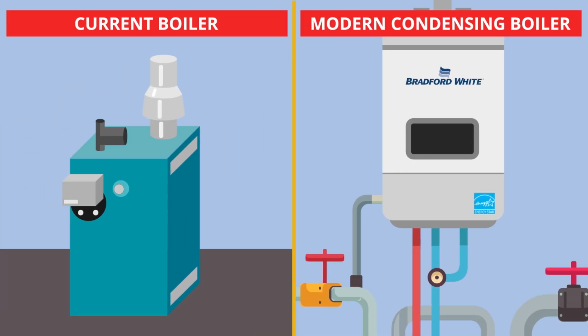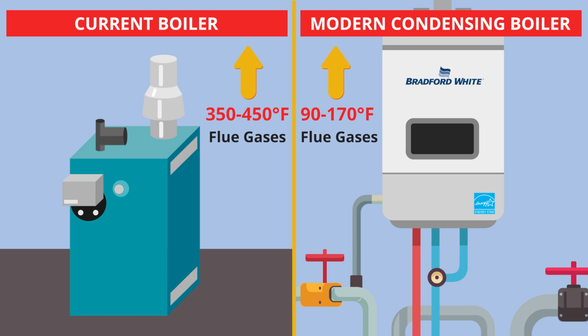Consider this. Your current boiler flue gases go up the chimney at 350 to 450 degrees Fahrenheit. With a modern condensing boiler, flue gases go up the chimney at between 90 and 170 degrees Fahrenheit. This boiler takes the heat that would have gone up the chimney and puts it back into your heating system. In short, the cooler the exhausted flue gases, the more efficient your boiler becomes.